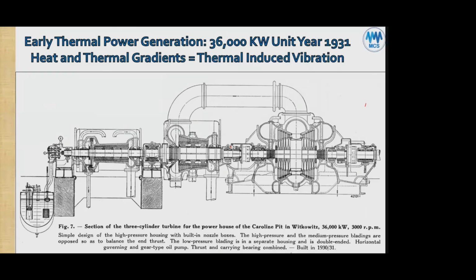They think that ISO VG32 is lighter oil, therefore it's great, it's high efficiency, means it's not having much shearing, and we have lower thermal losses in the bearings. And it's still doing the lubrication job. Yes, it's doing the lubrication job, but you're walking close to the edge of a cliff. The ISO VG32 oil at the bearing average temperature in the bearing loaded film area, let's assume it's 160 degrees Fahrenheit average temperature at the bearing loaded at the highest eccentricity ratio, which is the closest the shaft gets to the bearing. The average might be 160.